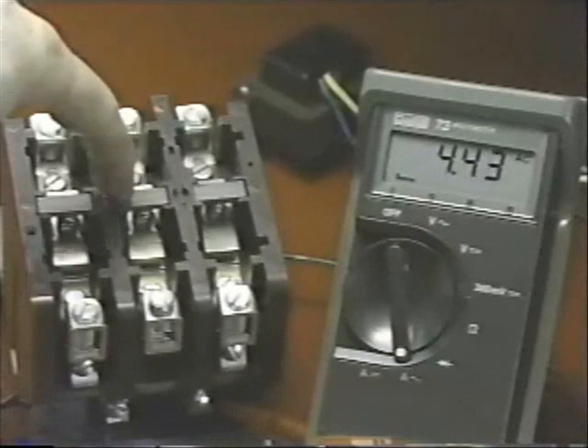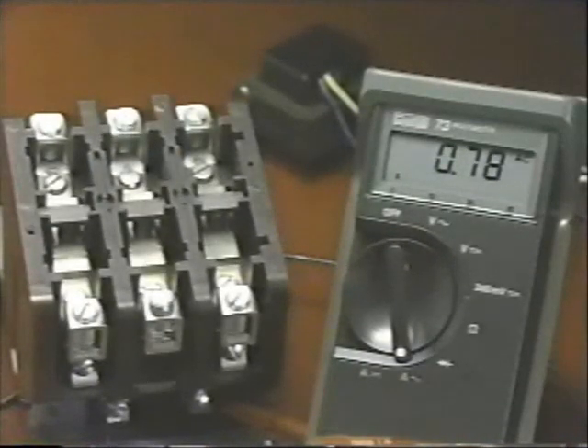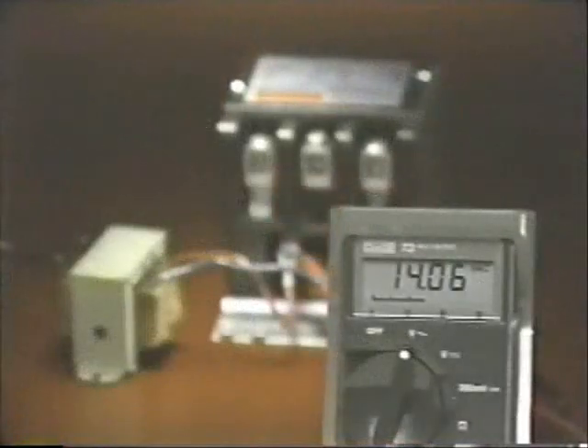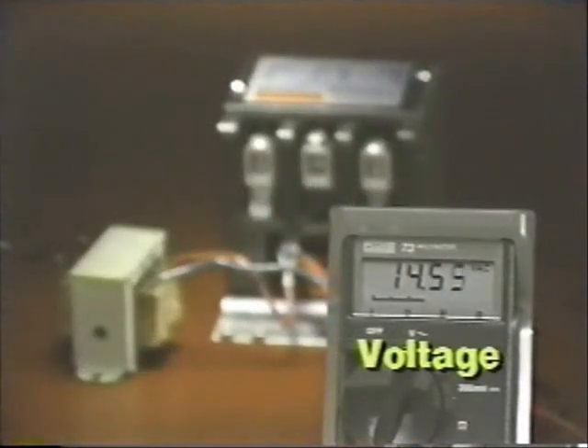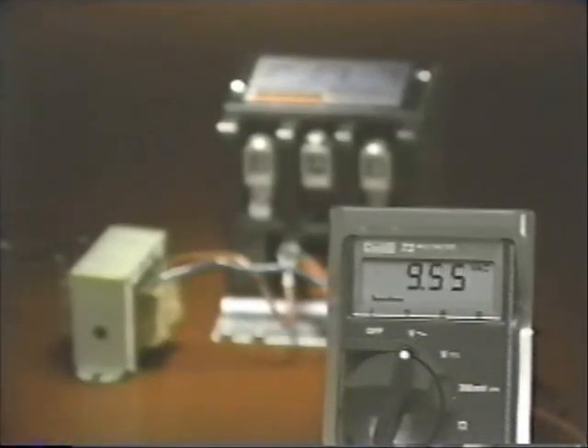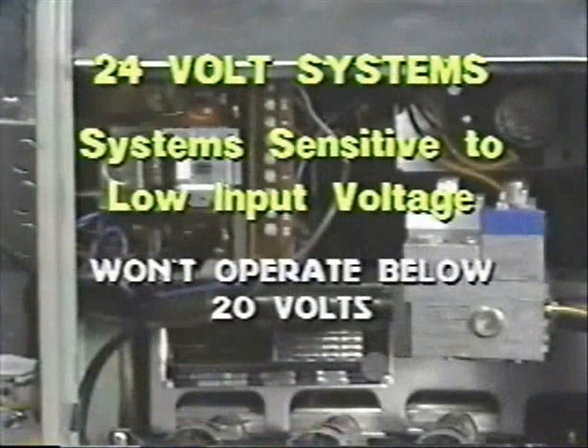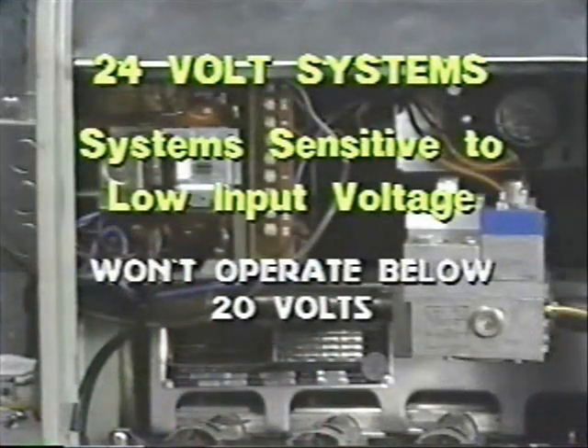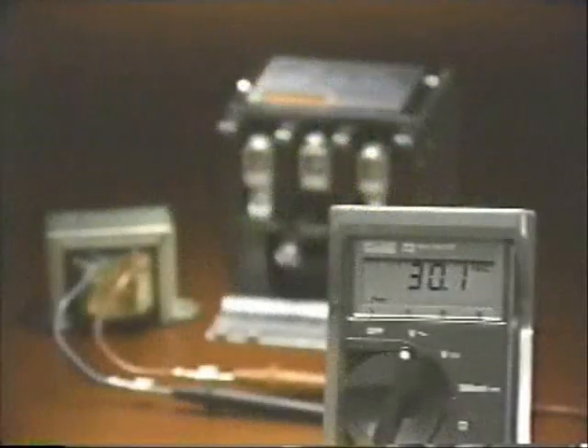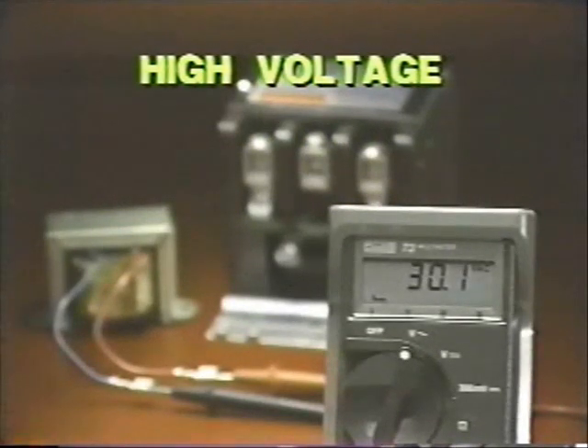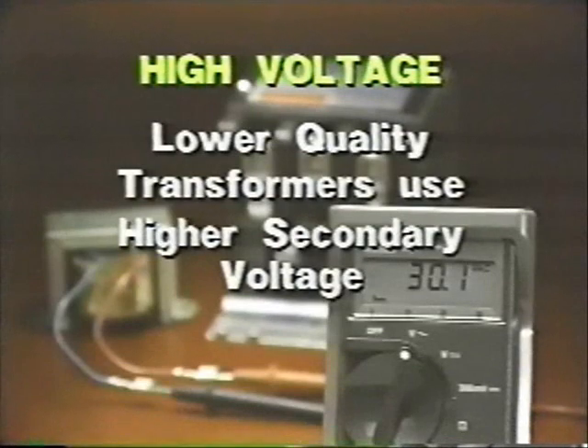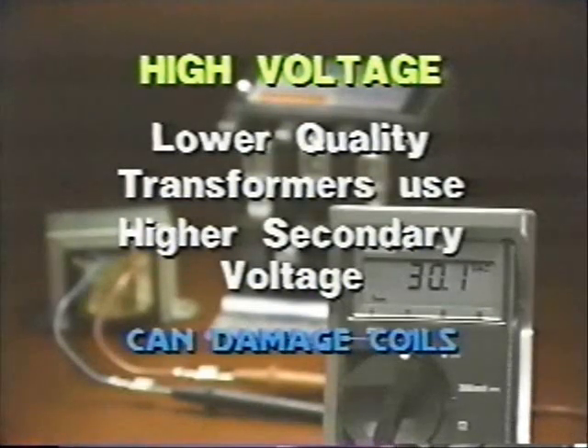Some transformers, however, fail to deliver adequate voltage under heavy loads, and size isn't always the problem. If a transformer's voltage drops off too much under inrush conditions, it may not be able to pull in all the necessary loads simultaneously. Some control systems are very sensitive to input voltage and simply won't operate if it drops too low, say below 20 volts on a 24-volt system. On the other hand, voltage that is too high can also cause problems. This is important to remember because lower quality transformers often compensate for poor voltage regulation by using a higher secondary voltage. Under light load conditions, high voltage can damage coils and other control circuit components.